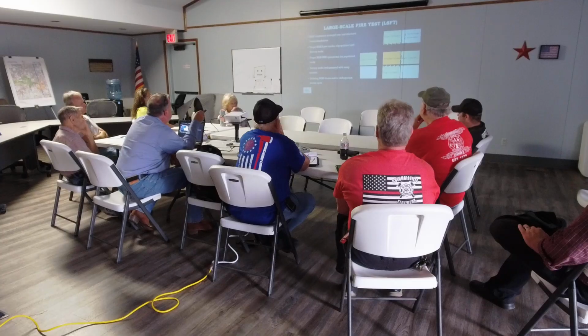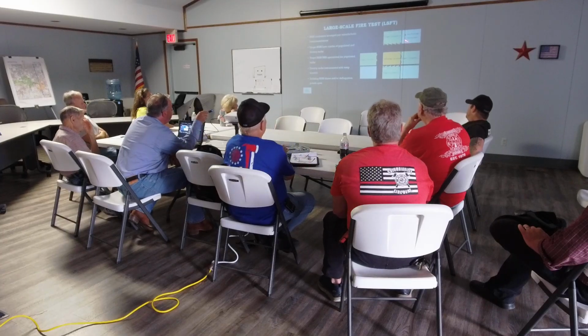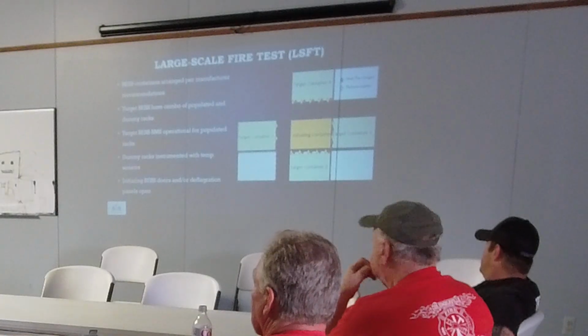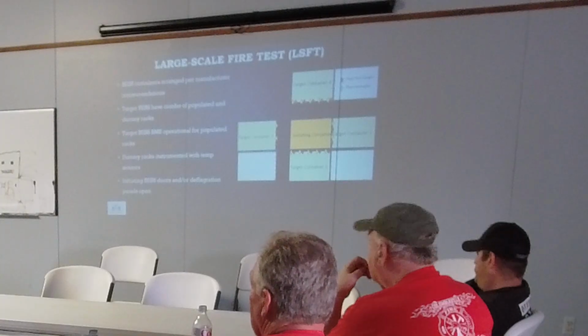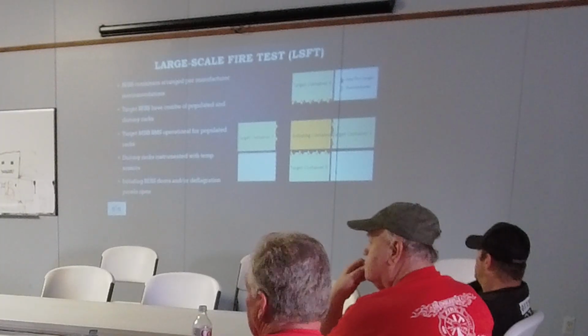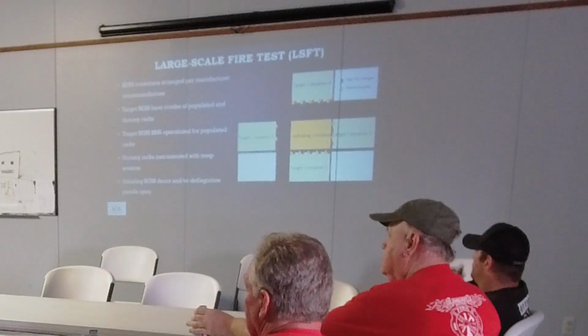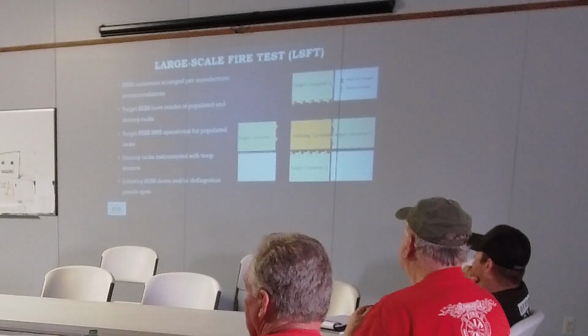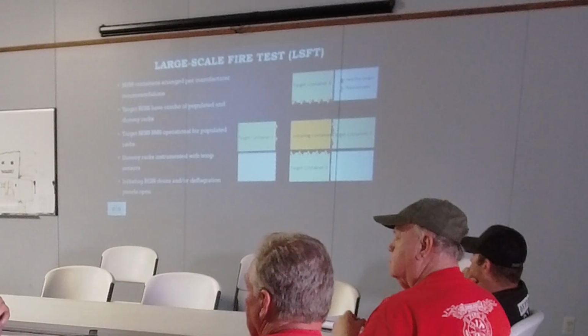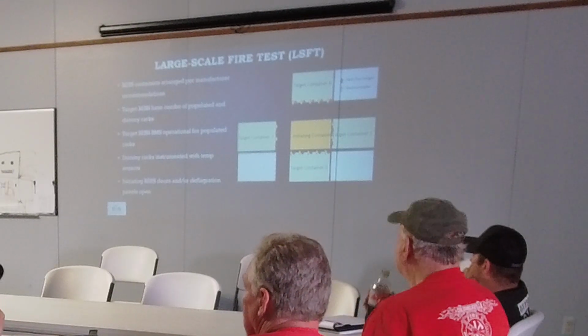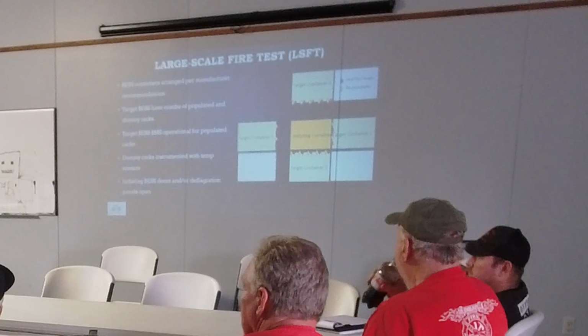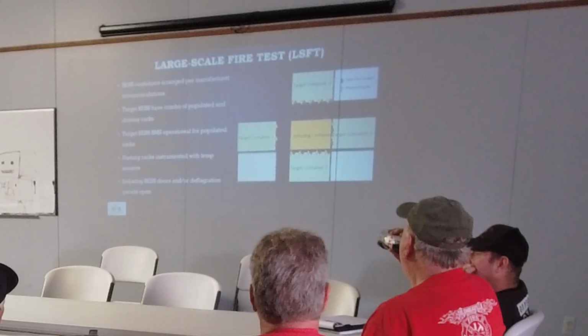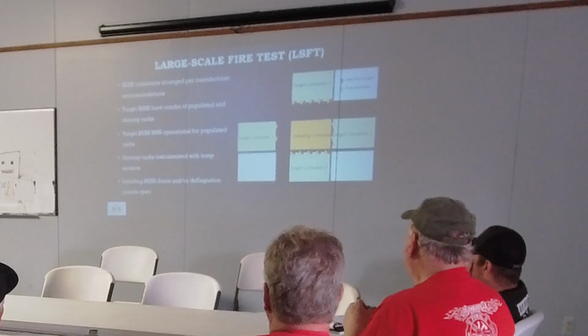This test specifically determines the required spacing minimums between containers. That spacing minimum is then transferred for that battery model to the site design lines. So if they say you can't be closer than 3 feet or you can't pass this test, then you're not going to see them closer than 3 feet on the site.